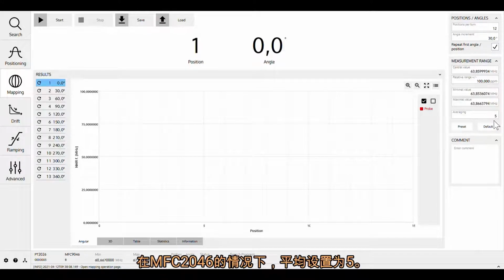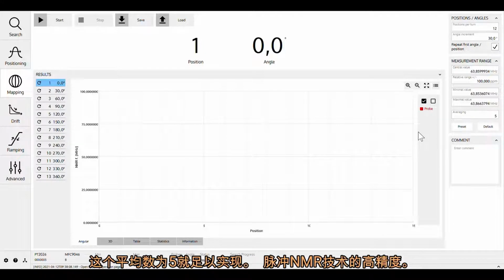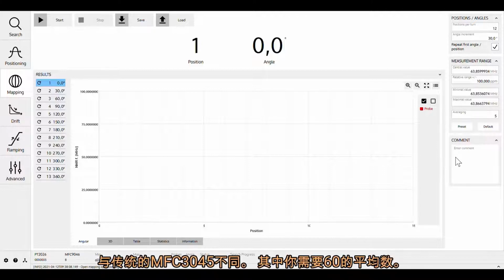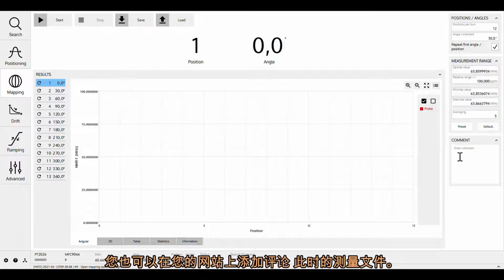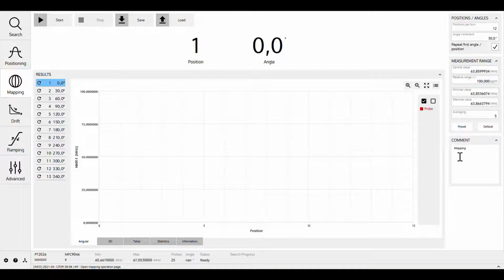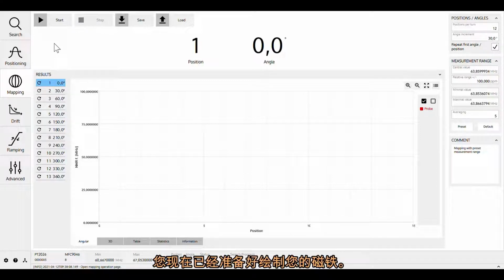Averaging is set to 5 in the case of the MFC 2046. This averaging of 5 is sufficient to achieve a high accuracy with the pulsed NMR technology, unlike with the legacy MFC3045 where you would need an averaging of 60. You can also add comments to your measurement file at this point. You are now ready to map your magnet.